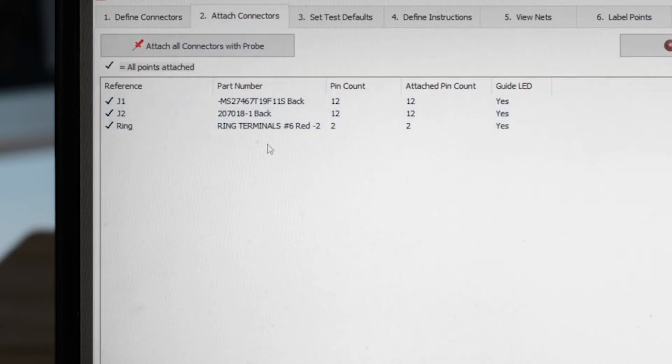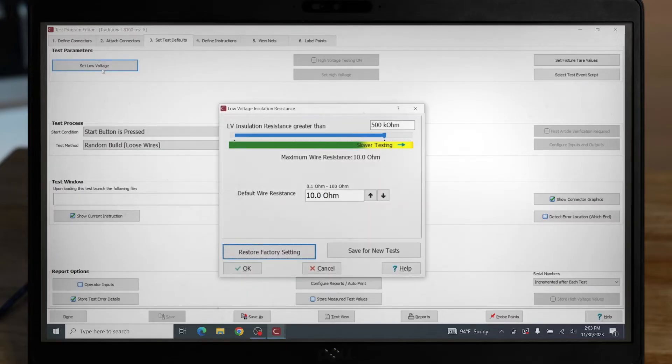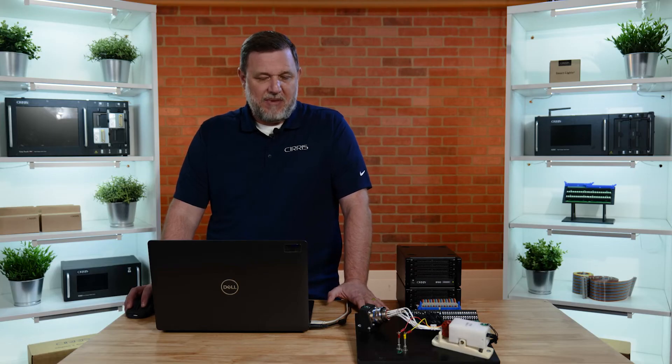Tab two is where we will be able to assign the system test points to the connectors. If we are using smart lights, we can also assign them here. Tab three, Set Test Defaults, is where we can set our test program defaults. We have the ability to set our low voltage connection resistance and our insulation resistance settings, and we can also change to a different test method if desired.